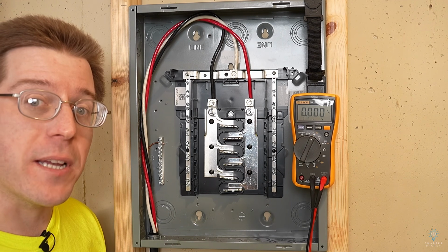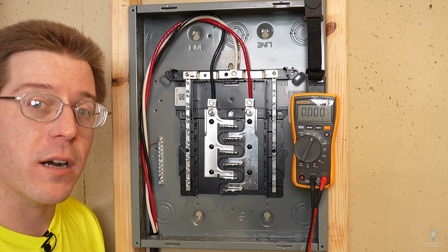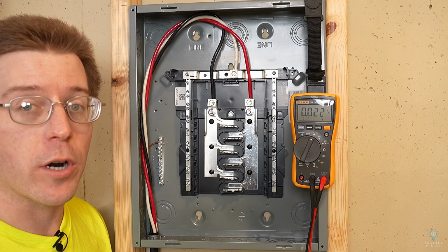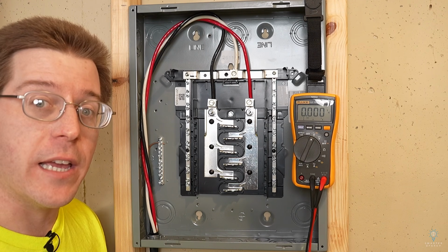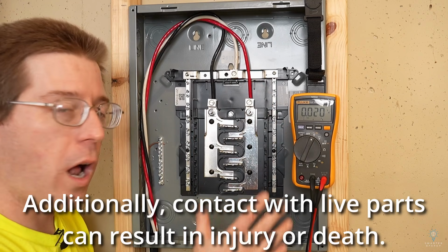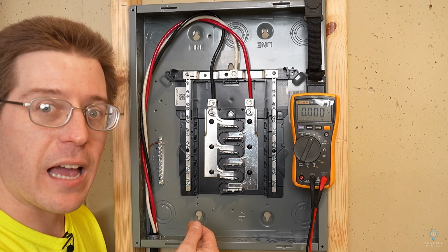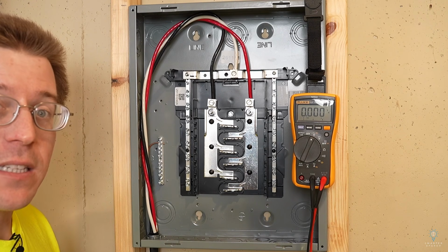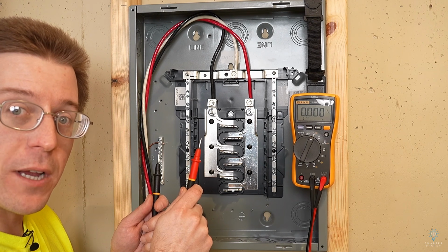If you were to drop something metallic across these bus bars, that could create an arc flash or an arc blast, which can cause severe injury or even death. So if you are not qualified to be in a live electrical panel, you should not be in a live electrical panel. In this case, this panel is live, so I can demonstrate some voltage measurements.